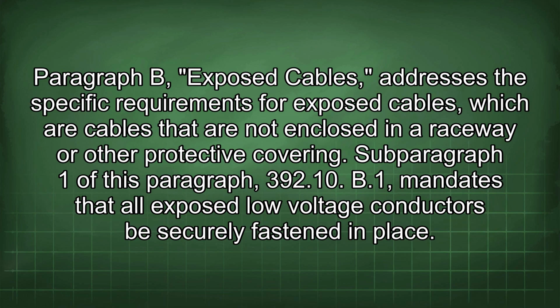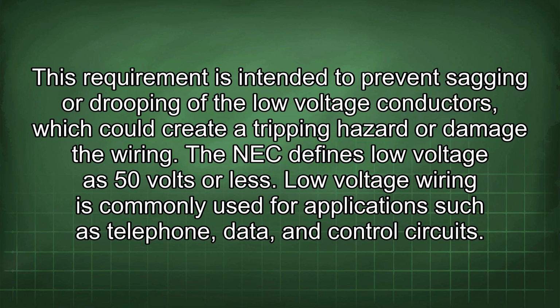Paragraph B, Exposed Cables, addresses the specific requirements for exposed cables, which are cables that are not enclosed in a raceway or other protective covering. Subparagraph 1 of this paragraph, 392.10b(1), mandates that all exposed low-voltage conductors be securely fastened in place. This requirement is intended to prevent sagging or drooping of the low-voltage conductors, which could create a tripping hazard or damage the wiring. The NEC defines low voltage as 50 volts or less.